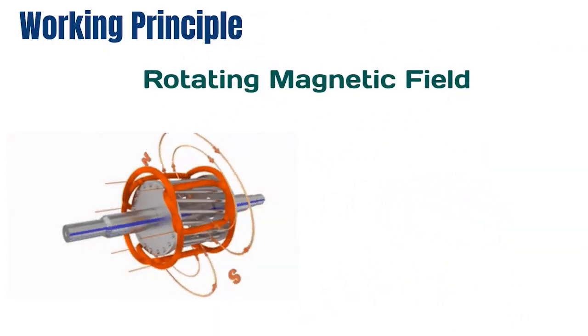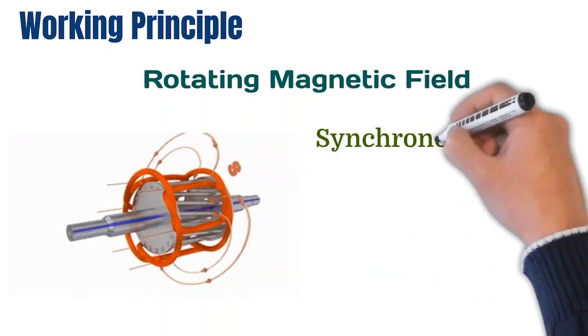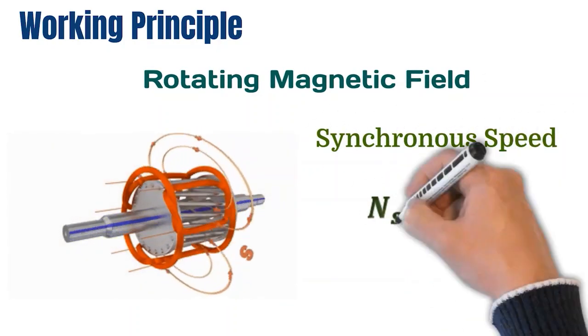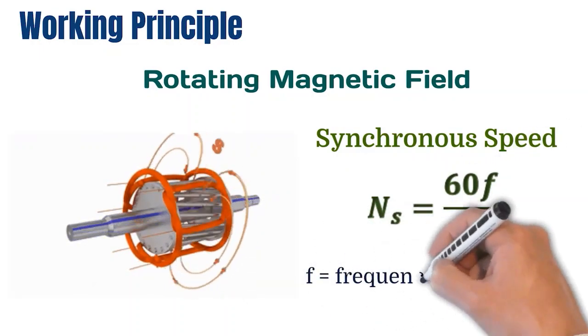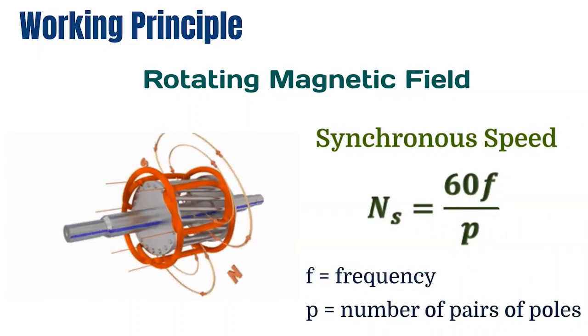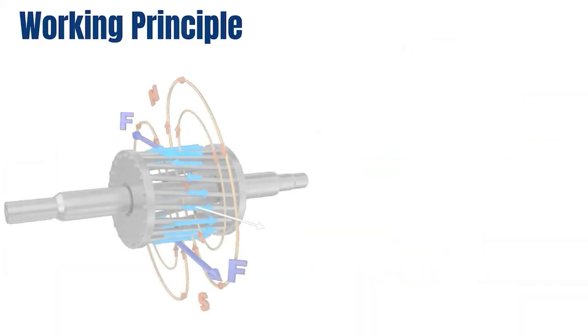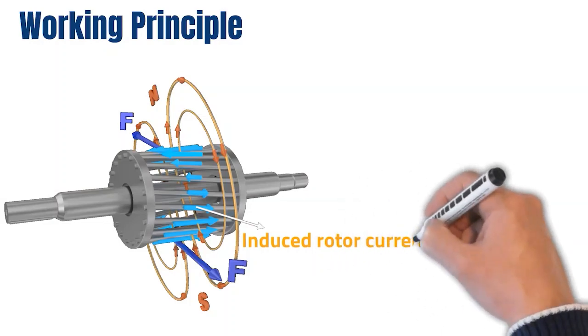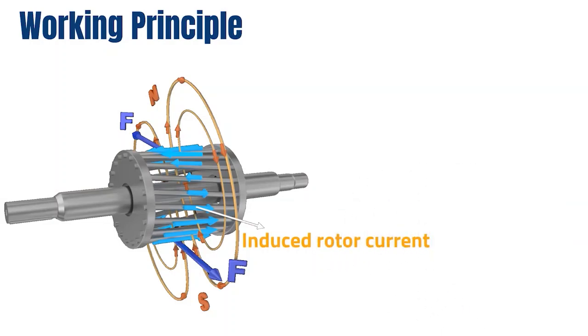When a three-phase voltage of constant frequency is applied to the stator winding, a rotating magnetic field is created in the air gap. This field rotates at synchronous speed, which can be derived using the synchronous speed equation. This rotating magnetic field is sensed by the three-phase winding in the rotor, inducing a balanced three-phase voltage. The rotor winding is closed using end rings, so the induced voltage creates a three-phase current. This rotor current reacts with the air gap flux and produces a torque to rotate the rotor.